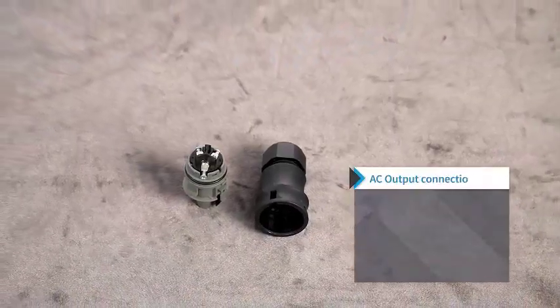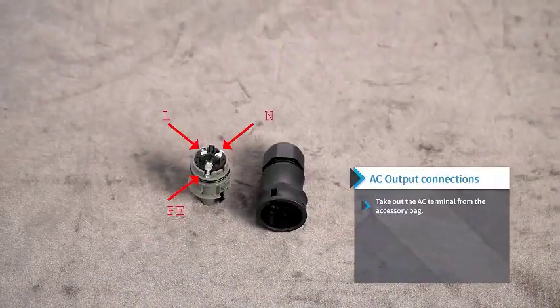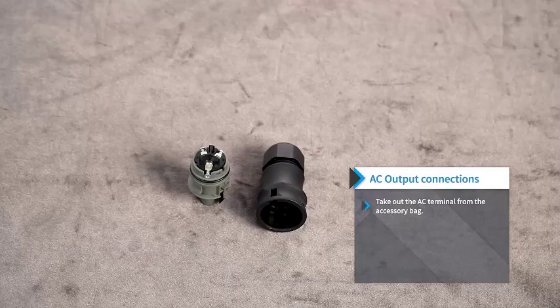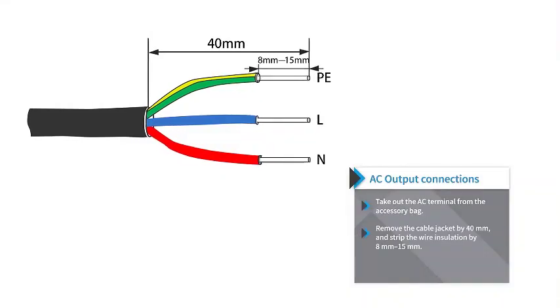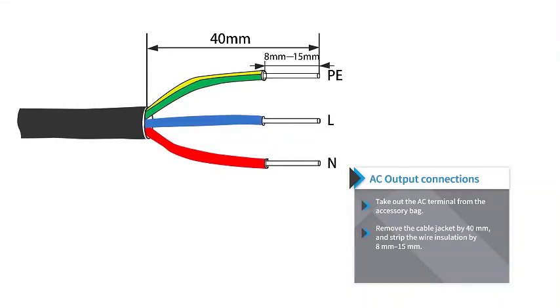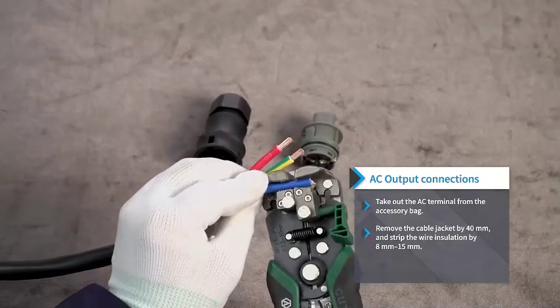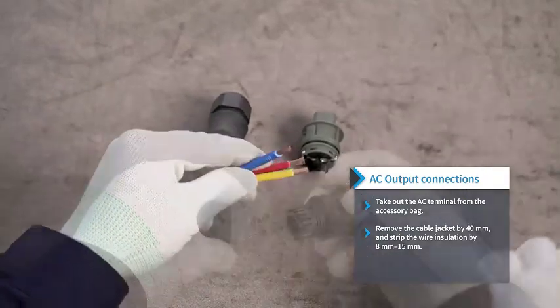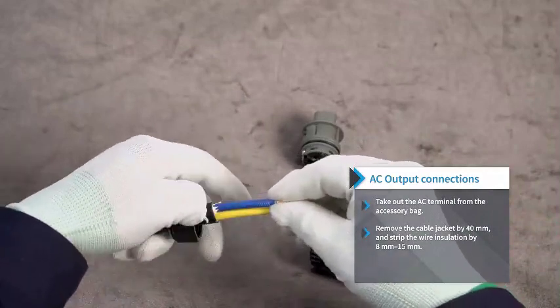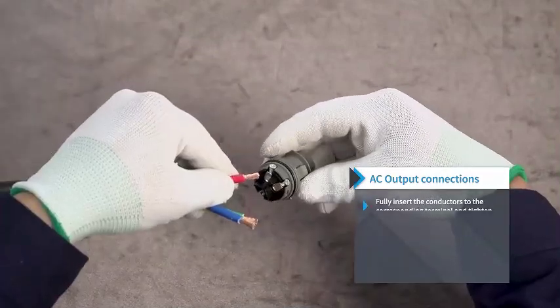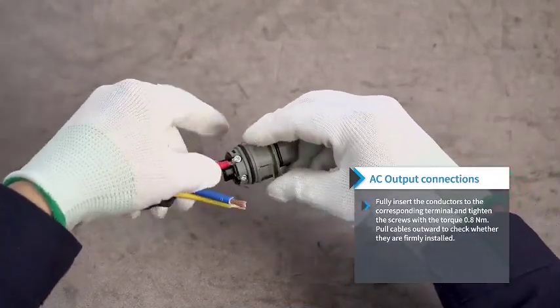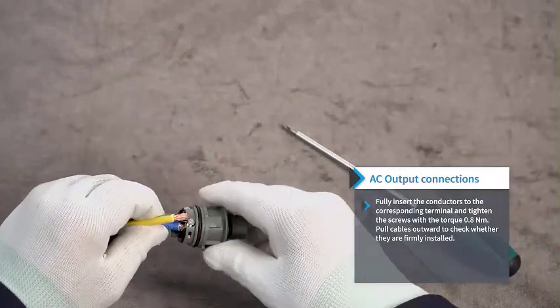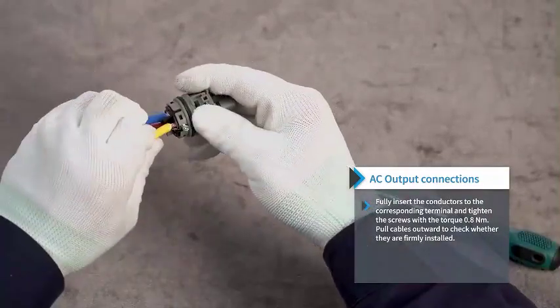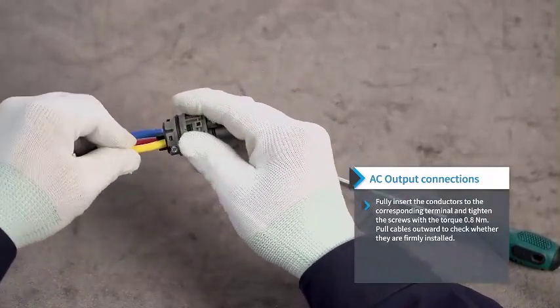AC output connections. Take out the AC terminal from the accessories bag. Remove the cable jacket by 40 mm and strip the wire insulation by 8 mm to 15 mm. Fully insert the conductors into the corresponding terminal and tighten the screws with a torque of 0.8 Nm. Pull cables outward to check whether they are firmly installed.